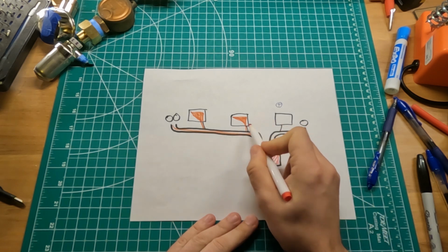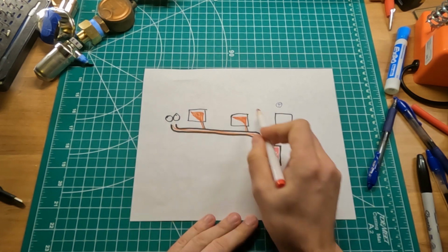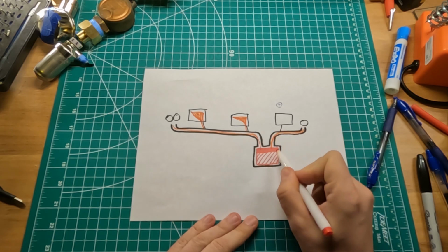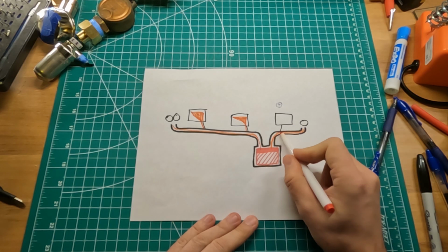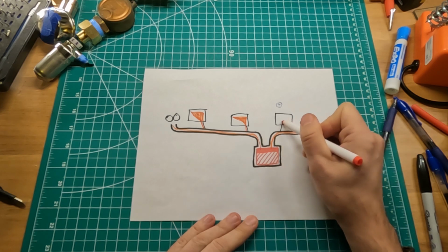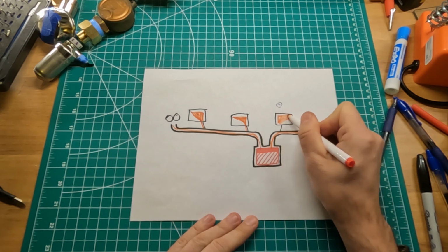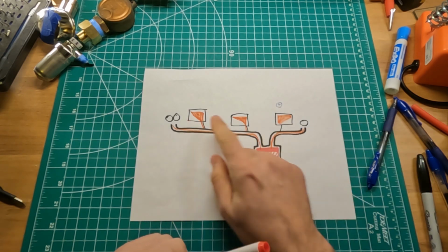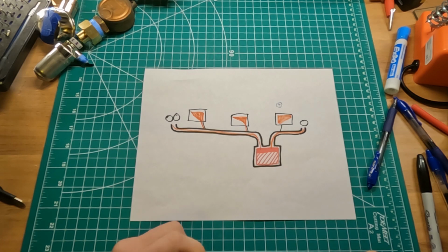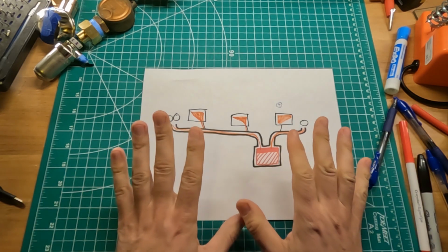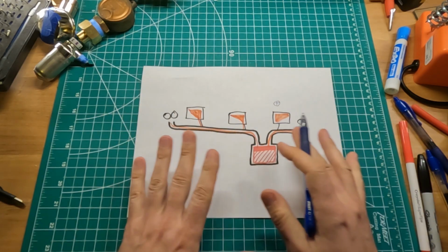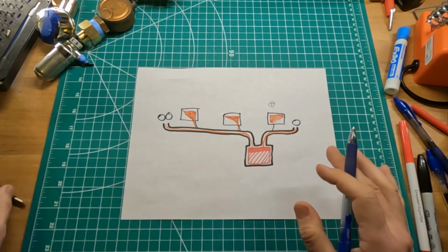And only when this leg is satisfied, then the steam boiler finally fills up this leg with heat, with steam, and then this radiator fills up. The thermostat gets satisfied, the boiler shuts down, and everybody's happy because all the radiators heat up evenly.